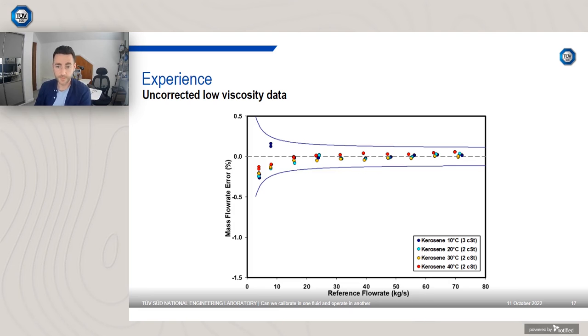In terms of experiences, what I have here is just some kerosene data for a Coriolis meter. So this is what are termed uncorrected low viscosity data. On the x-axis, I have reference flow rate. On the y-axis, I have mass flow rate error. So that is a deviation from the Coriolis meter compared to our reference, in this case, the gravimetric reference system that we have here at NEL.